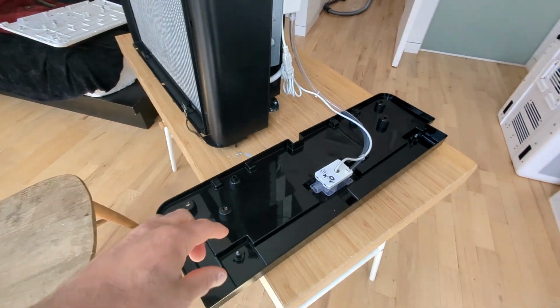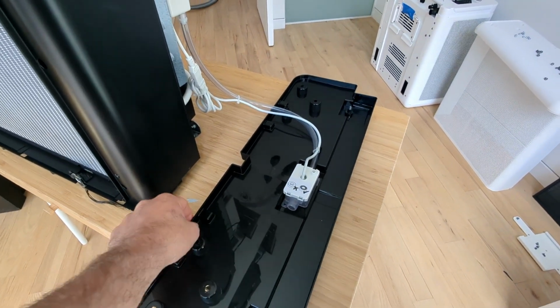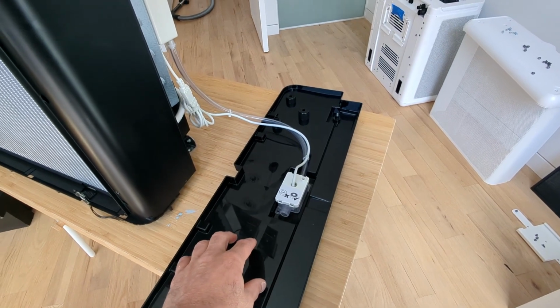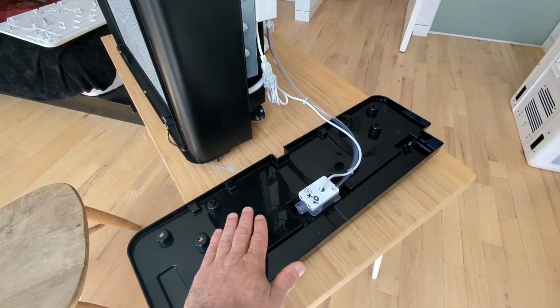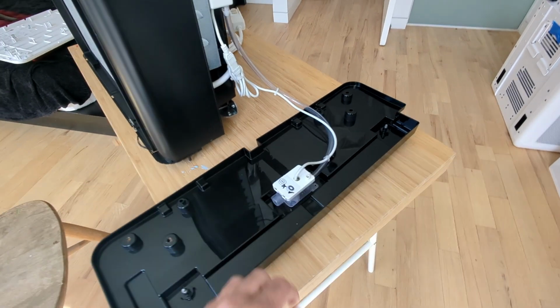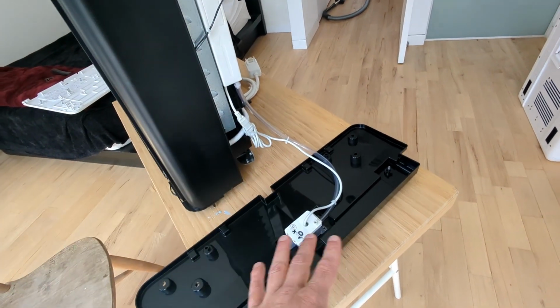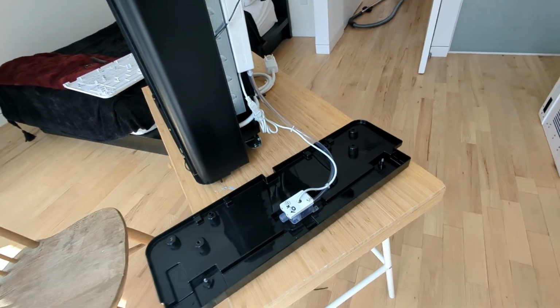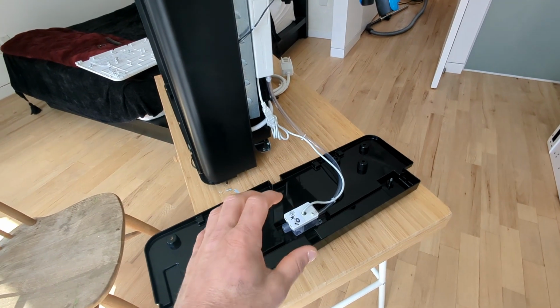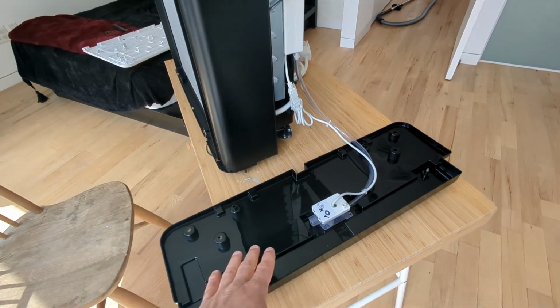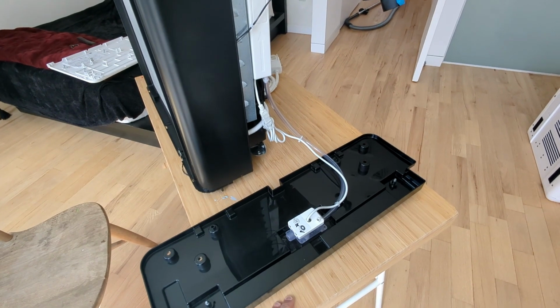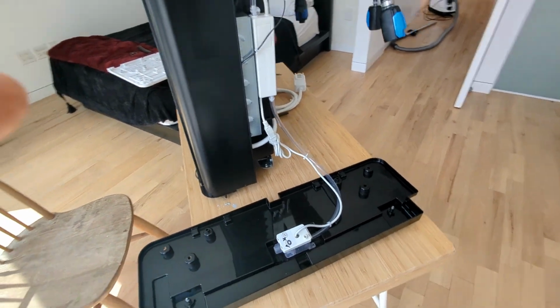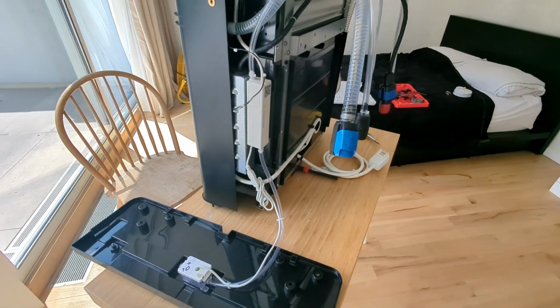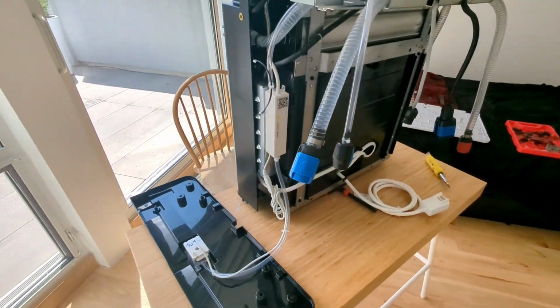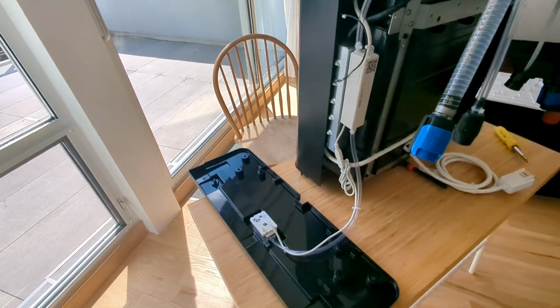Another missed opportunity: I would love to see a backup liquid sensor on the side of this tray that would tell the computer anytime this tray got too full. If that liquid sensor ever triggered, it means something went wrong somewhere in the condensate system. Doesn't matter where, but whenever you see that, you just turn the whole thing off and show the user an error. If you kept running the system in that state, eventually this tray is going to overflow and spill out, and spilled water going into the person's home is always a very bad thing that can cause a lot of damage. So it's worth the extra couple of pennies to put a backup sensor there.